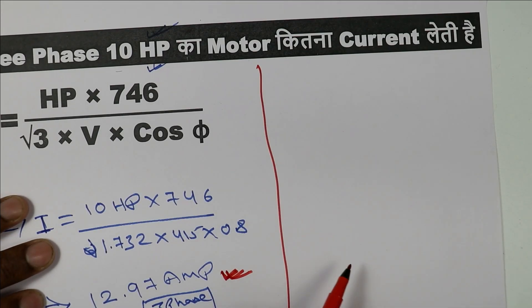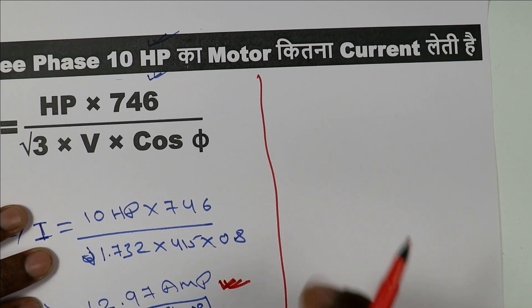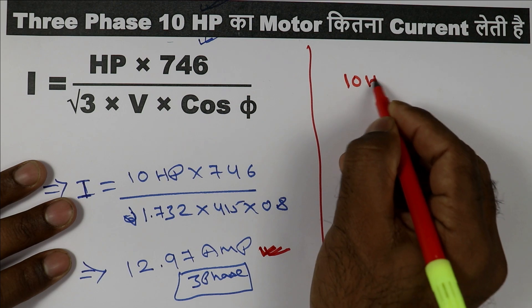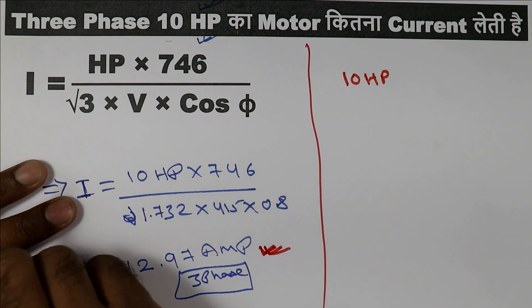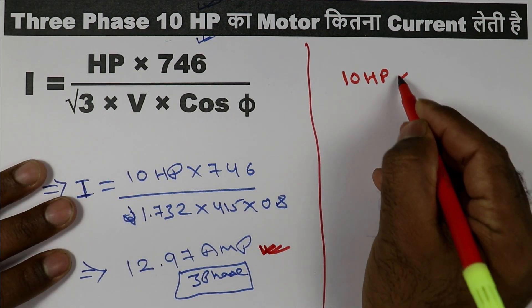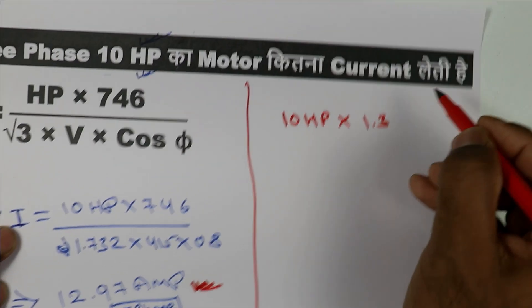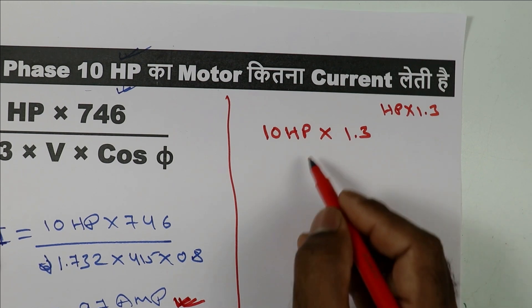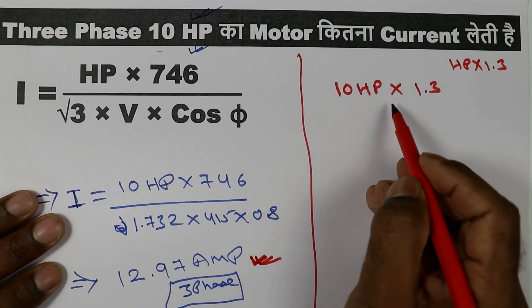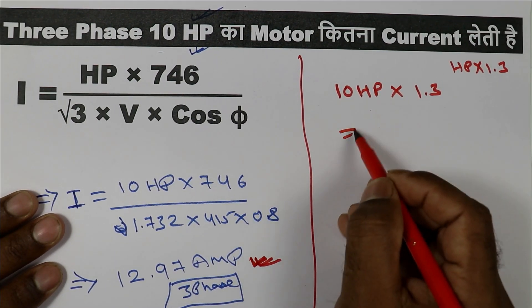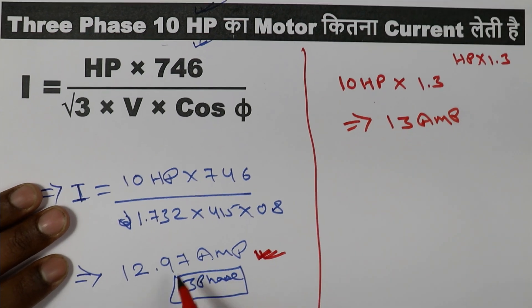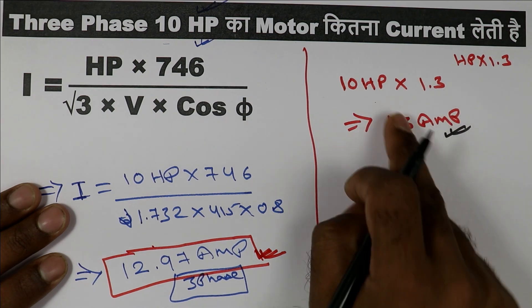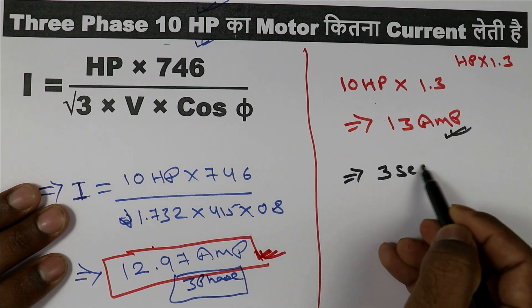Now for the short trick: for a 3-phase horsepower motor, simply multiply the horsepower by 1.3. We have a 10 HP motor, so we multiply 10 HP by 1.3, and we get the answer as 13 ampere. The exact answer was 12.97 ampere — you can see it is almost the same. By using this short trick, you can give the answer in just 3 to 5 seconds.